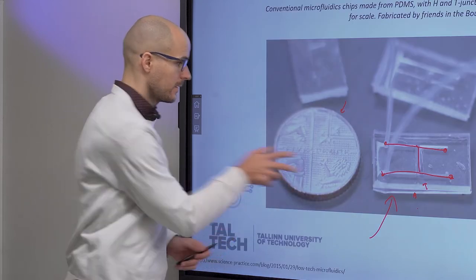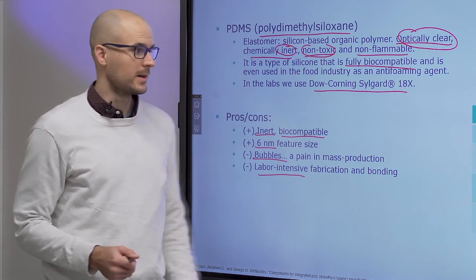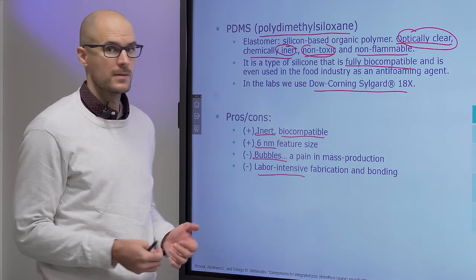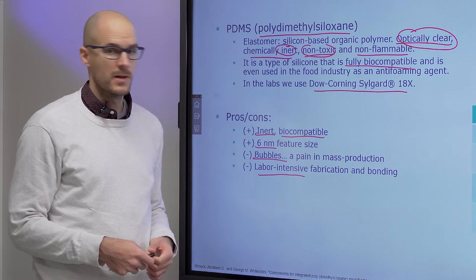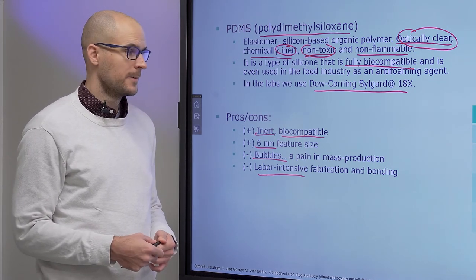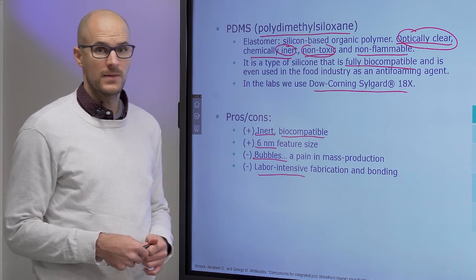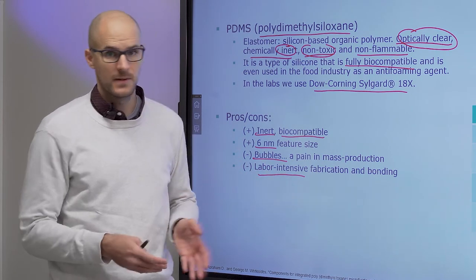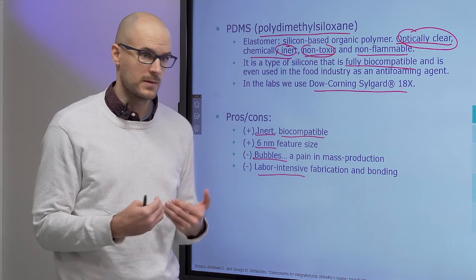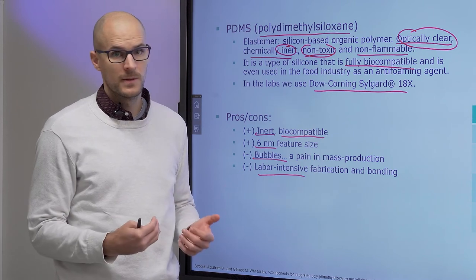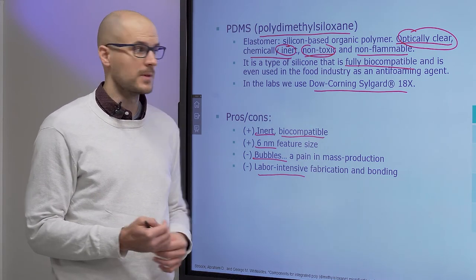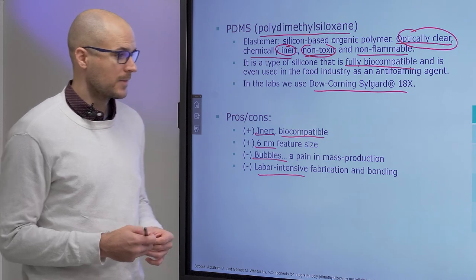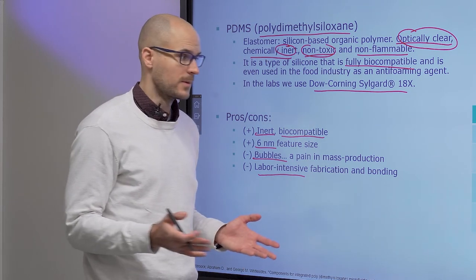Also, molding PDMS is highly manual — you need a lot of steps done by skilled personnel, which does not really help mass production of PDMS-based devices. Not to mention the other disadvantages it has compared to injection molded plastics, which is very highly standardized. Because of how common injection molding is nowadays, it is also quite cheap. You can easily find companies that can fabricate molds and perform the injection molding for you, because it is used everywhere in industry for various purposes.